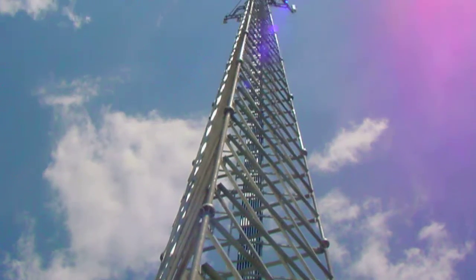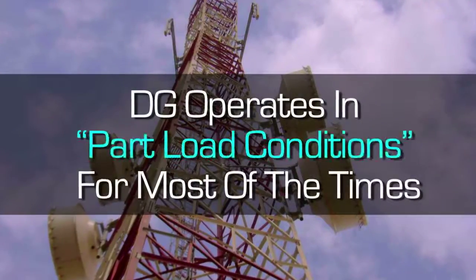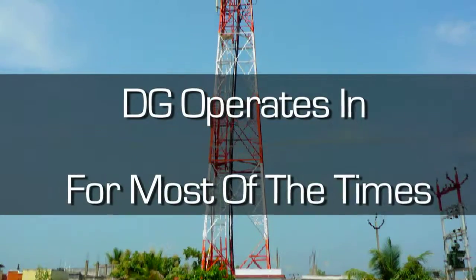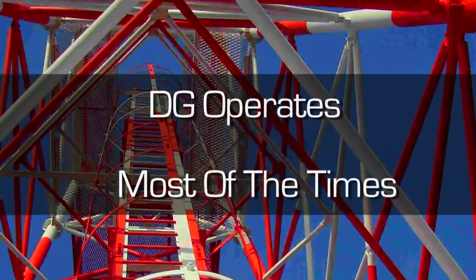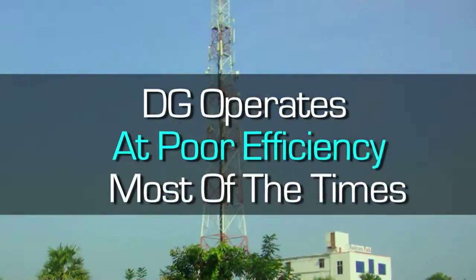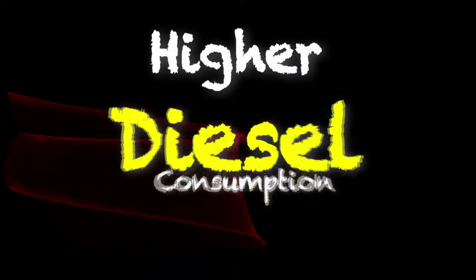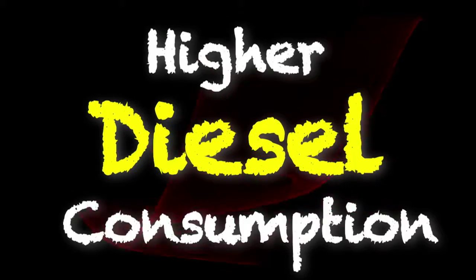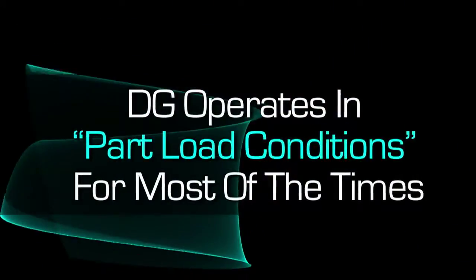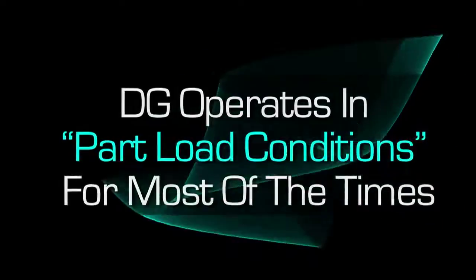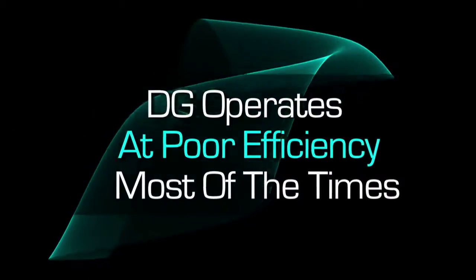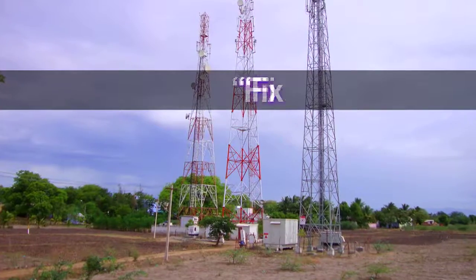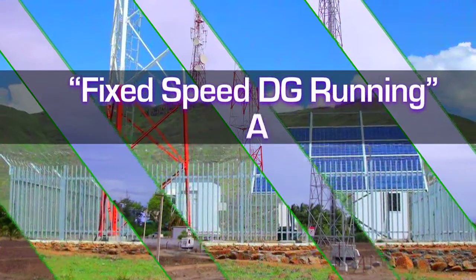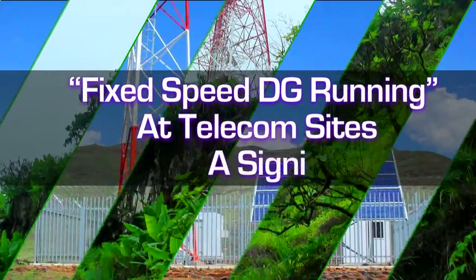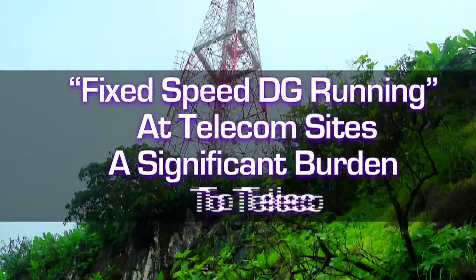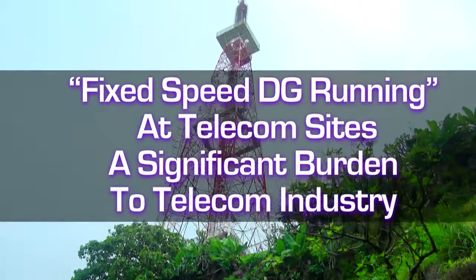At telecom sites all over India, the DG operates in part load conditions for most of the time. Thus, the DG operates at poor efficiency most of the time, resulting in higher fuel consumption than what is actually required. Due to this low fuel efficiency, the site operating costs for the telecom industry go up. In summary, we can say that the fixed speed DG running at telecom sites results in a significant burden to the telecom industry due to high fuel expenses.